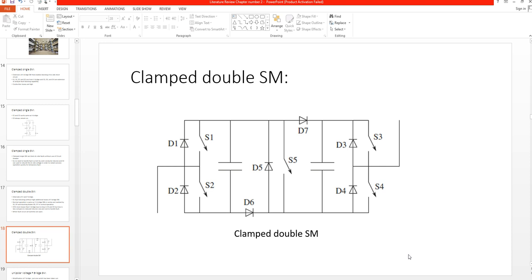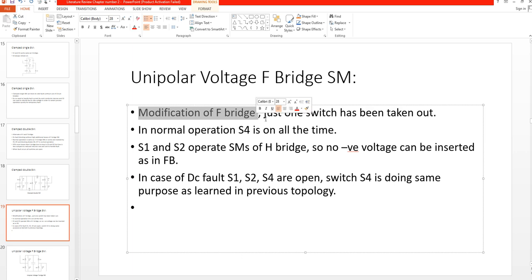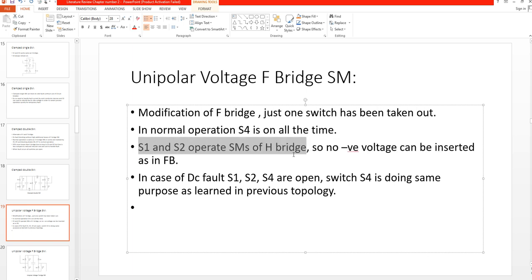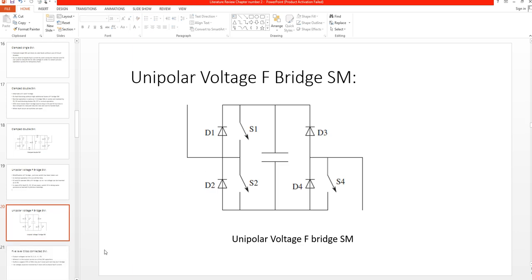The next topology is the unipolar voltage full bridge submodule topology. It is basically a modification of the full bridge where only one switch has been removed. In normal operation, S4 is on all the time and S1, S2 operate the submodule as a half bridge, so no negative voltage can be inserted as in a full bridge. In case of a DC fault, S1, S2, and S4 are open.